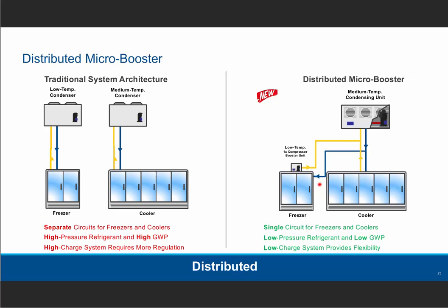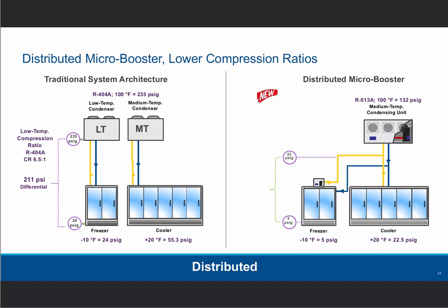And the advantage of that is that we have low compression ratios, low discharge temperatures. Instead of having a compressor that discharges at higher compression ratios, this one's much less. So if we take the system on the left at a minus 10 saturated suction and 24 pounds of 404A with 100 degree condensing, there's 211 pounds of lift with a compression ratio of 6.5 to 1 on the low temp. And incidentally, this changes with ambient.